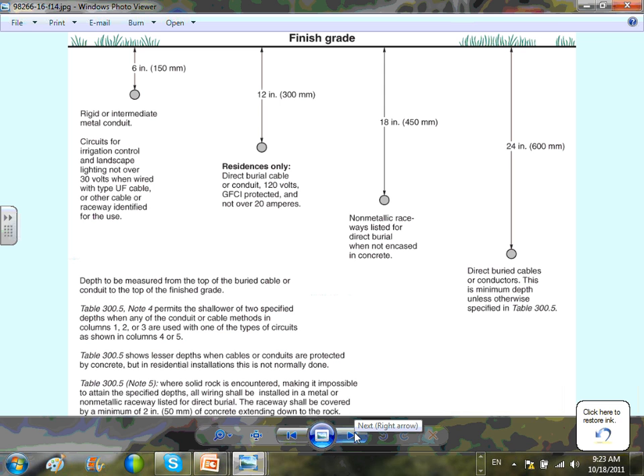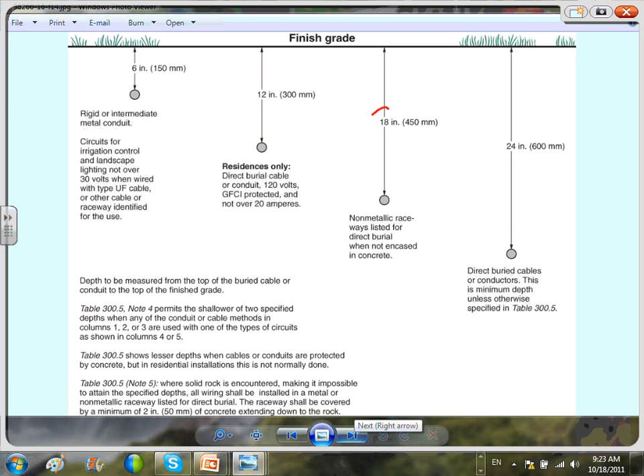Please look at the depth, very important, guys. And as I said, you are going to be in 99%, 18 and 24. As engineers, guys, when we have direct buried conduits, most of the time we specify 24 inches to the top and move on. If you have PVC, though, you can go as low as 18. This is only direct buried cable, 24. But as I said, when we specify even conduits, we specify them 24, more than what the code even has.